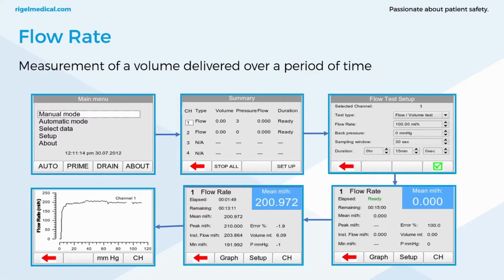But it won't actually carry out a test. It won't start measuring flow or elapsing any time until the infusion device begins to operate. And then once it begins to operate, it will measure, and the countdown will commence. And then you can also switch from these numerical values using the F2 or the second function key to go to the graph and see the on-screen analysis.